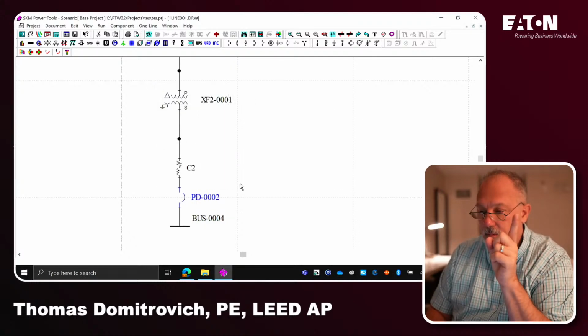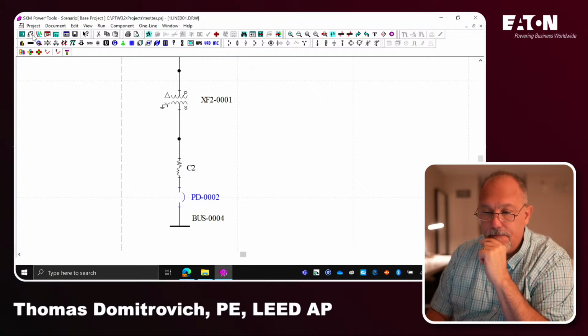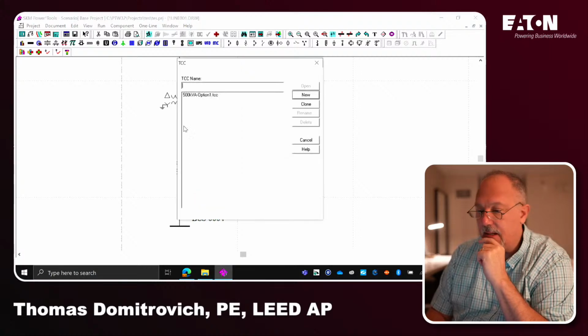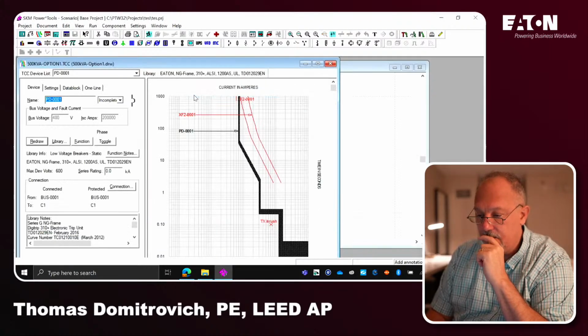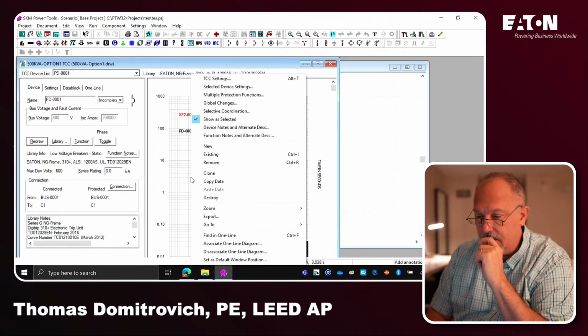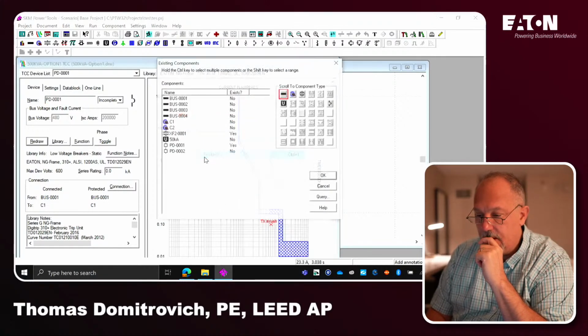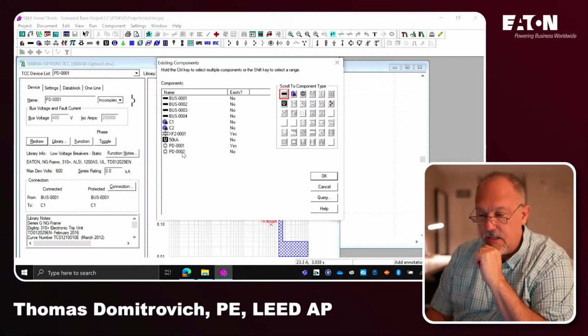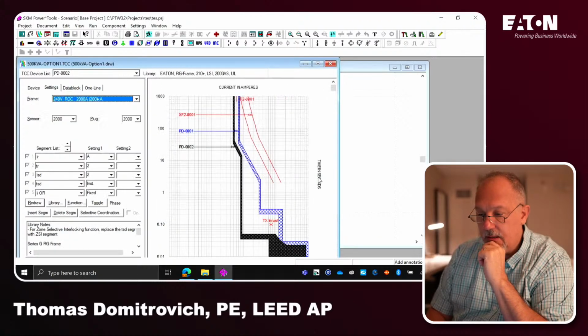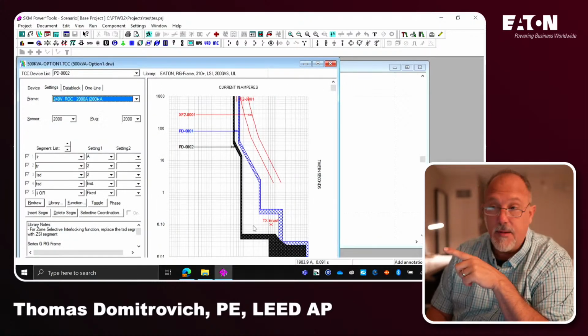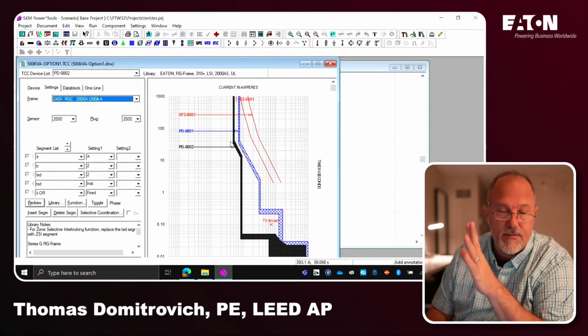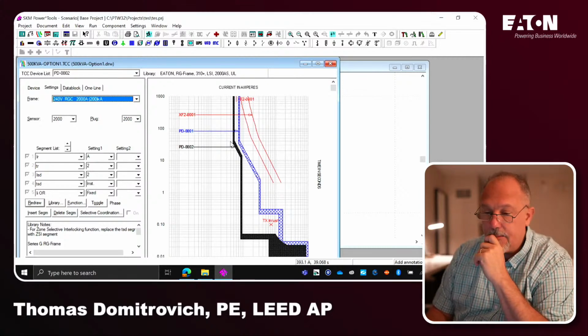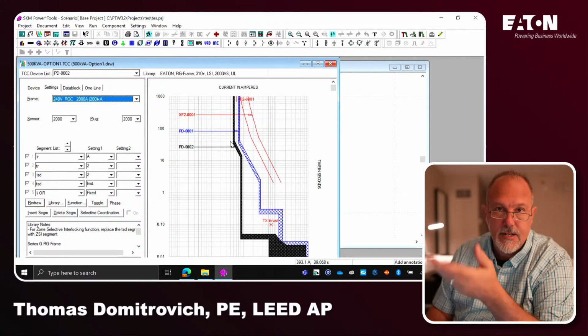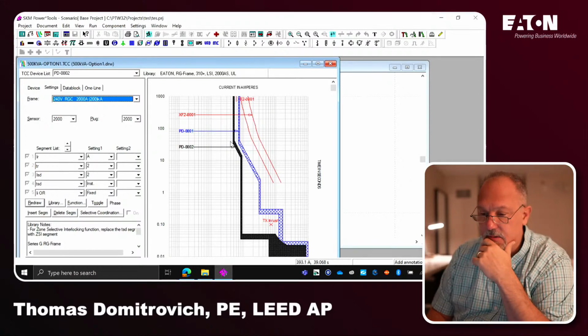All right, close. All right, so let's go back to the TCC. Let's go back to the time current curve. Let's pick this. We are going to add a device. We're going to add an existing device, which is PD2. Remember that. I hit OK. There is my downstream. Now, it doesn't matter if they overlap because the primary and secondary, they take out the exact same load, so that doesn't matter.